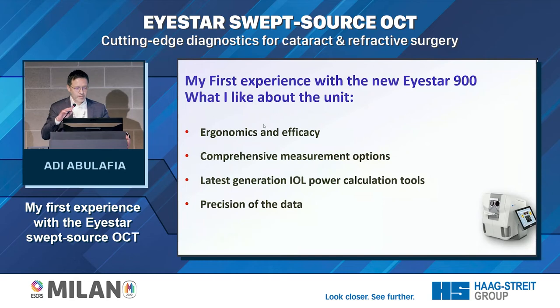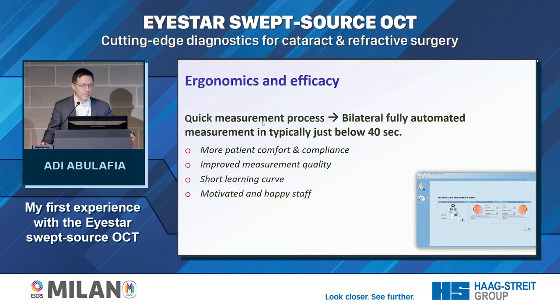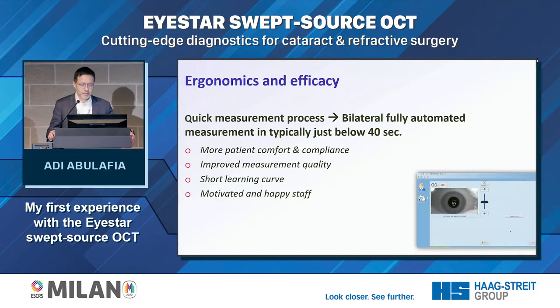I would like to share my first experience with the new Eyestar 900 and what I like about it. Starting with ergonomics and efficacy: the first thing that strikes you is the quick measurement process. You get bilaterally fully automated measurements in typically just below 40 seconds, which means more patient comfort and compliance, improved measurement quality, and a shorter learning curve for your staff.